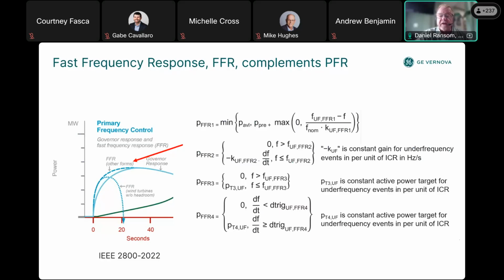Triggers for FFR are specified based on frequency deviation or the rate of change of frequency, df/dt, and active power targets for under frequency, as you can see in the math equations here. The IBR plant will sustain FFR for as long as the IBR plant energy resource is available or until supplanted by primary, secondary, and tertiary frequency response.